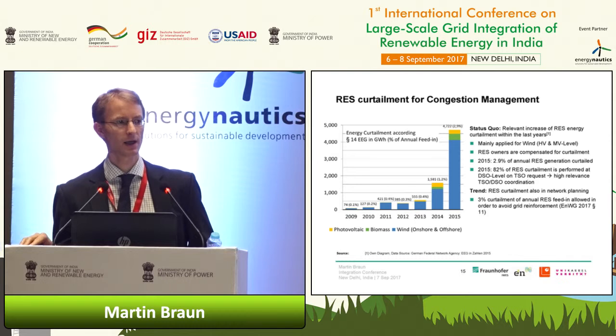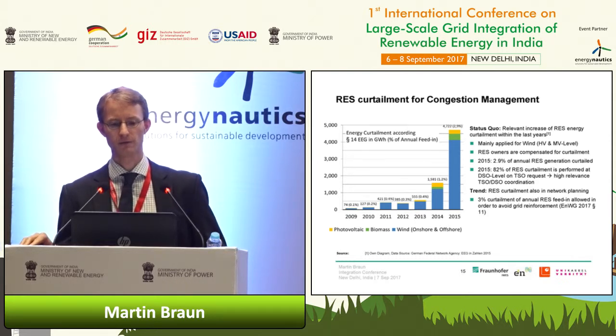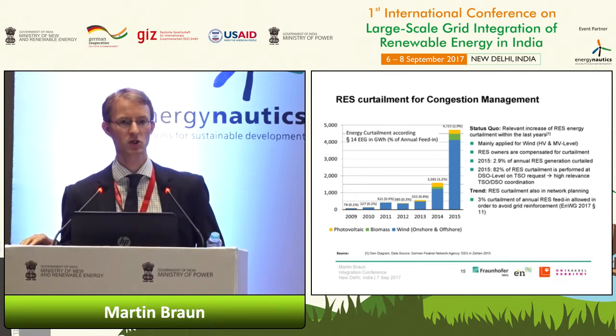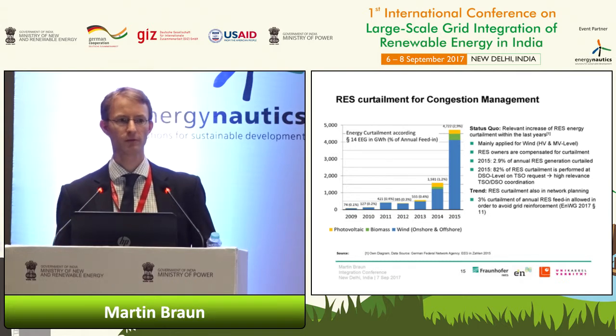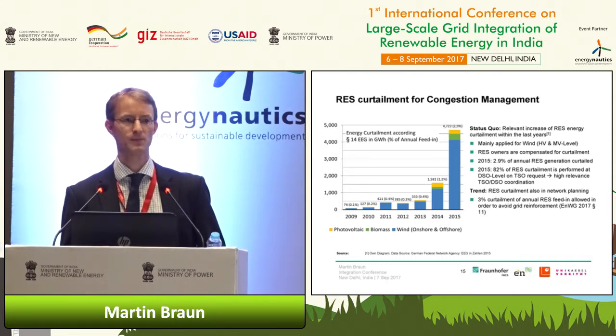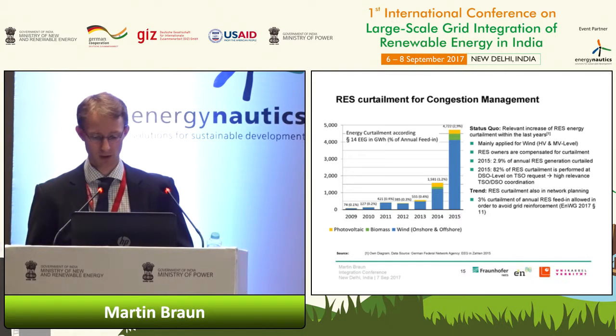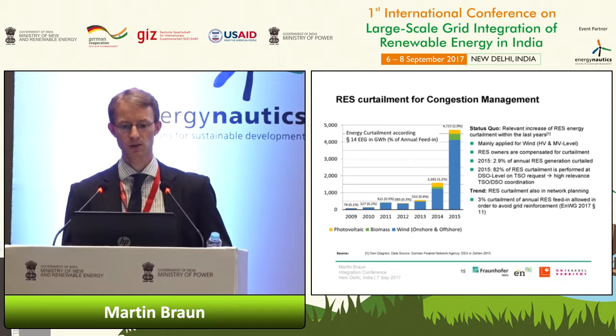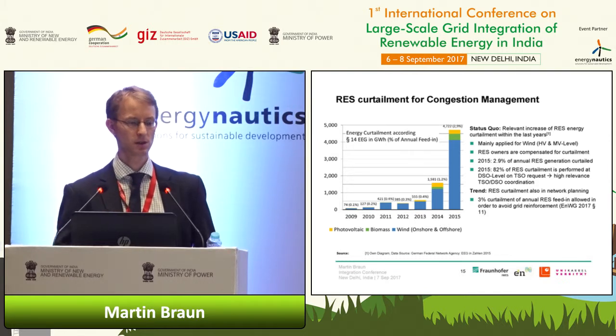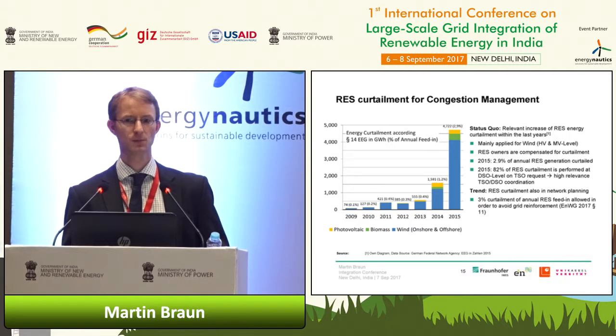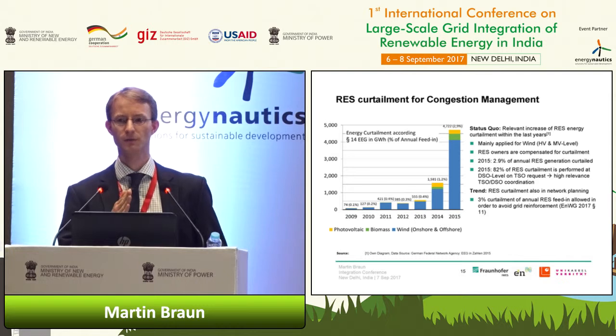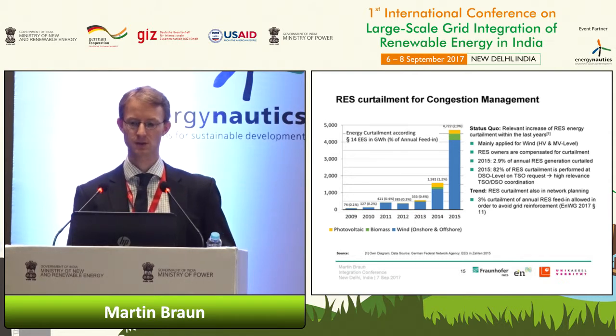Moving to active power curtailment - we've seen a steep increase in curtailment measures over the last years, a really steep growth. A few years ago it wasn't seen as a relevant issue; now about 3% of annual renewable energy production is curtailed because the grid can't absorb it, since grid reinforcement, especially in transmission, is delayed. So it's important to have control capability of distributed generation in the distribution system, down to medium and low voltage, to ensure sufficient controllability of this generation. If it's installed but you can't control it, you have a problem in case of system security issues.